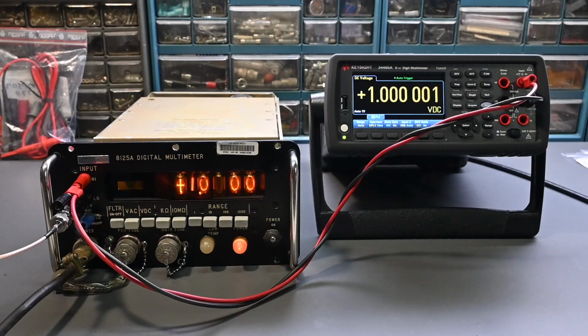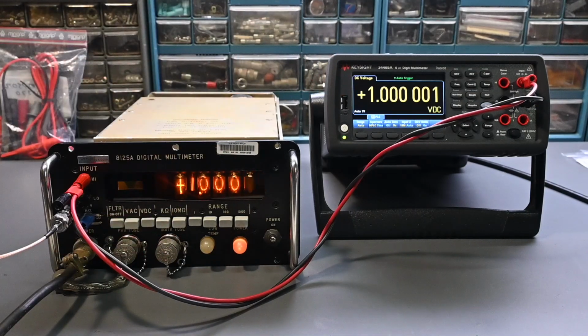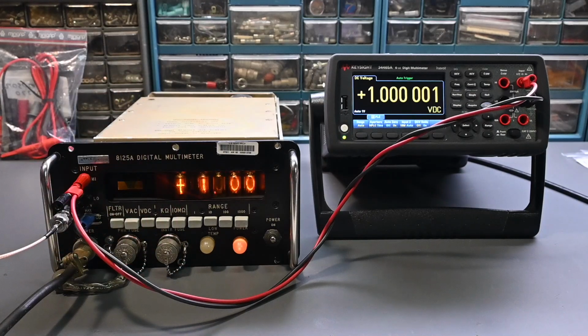All right, so you can see right now on the display it's showing 1 volt DC, and it's spot on 1 volt. We have 1 volt over there, so no problems. So if I go to the 10 volt range right here, of course it's still showing 1 volt, and I'll go over here to the DC calibrator and I'll change this over to the 10 volt range. So that's 10 volts right there. It'll have to settle in a little bit.